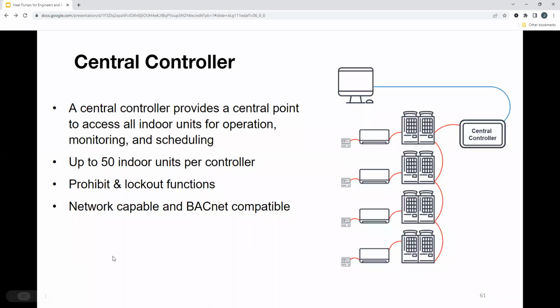So you can do all those controls just through this one central controller. You don't need any third-party integration whatsoever. If you install a heat pump, this is what comes standard with a manufacturer. Central controller can tie in all of these fan coil units and all the condensers.